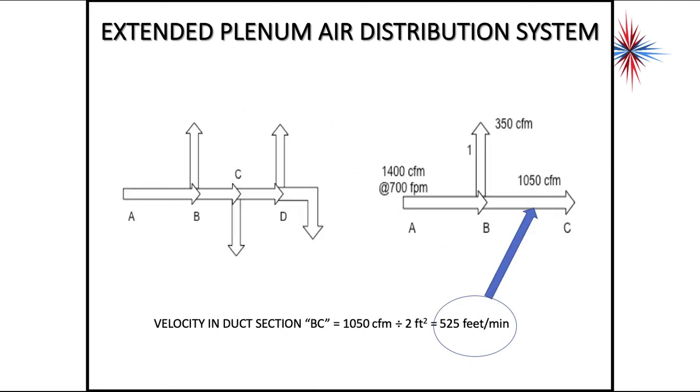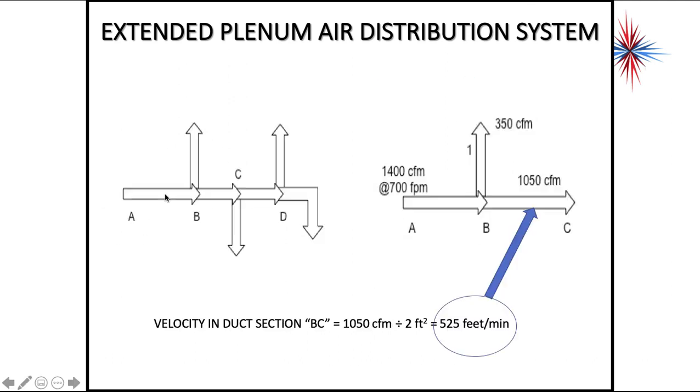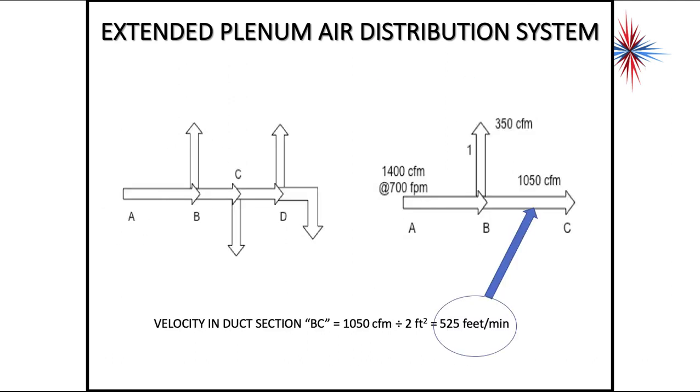So let's jump back here. We have my duct sections here. We have A to B, B to C, C to D, and then after D, we basically just have that single register left. So between B and C, which is this area right here, that's what this is showing. I'm losing 1,400 minus 350, so I only have left in this area 1,050. I know it's 525 feet per minute.